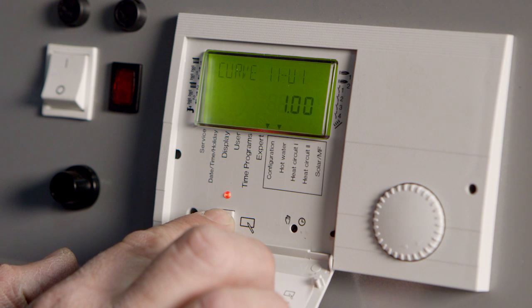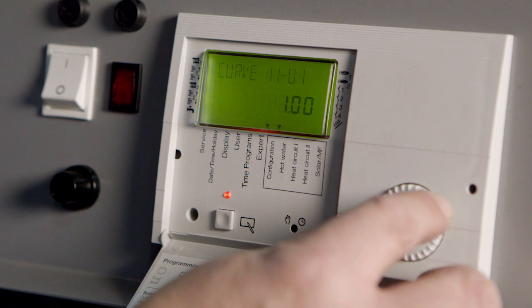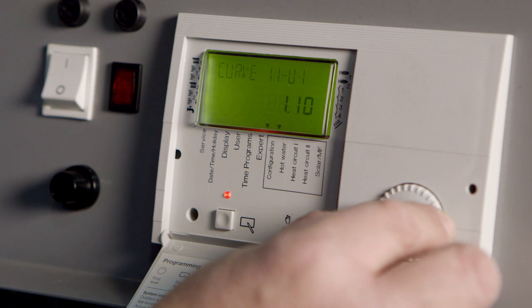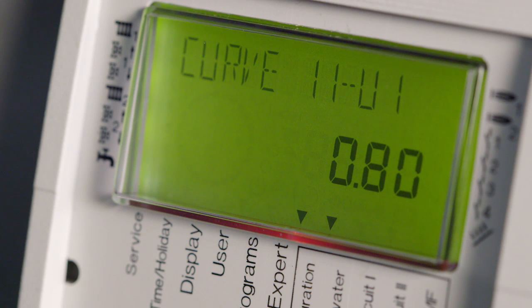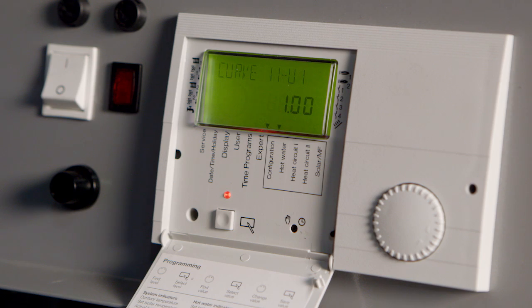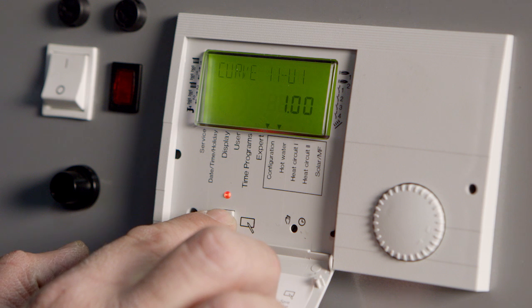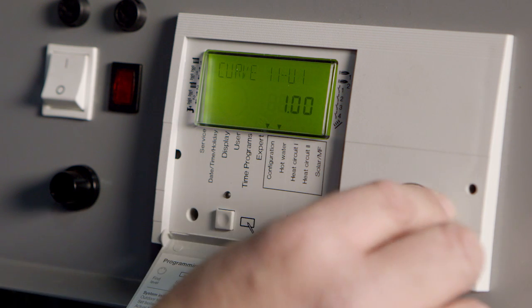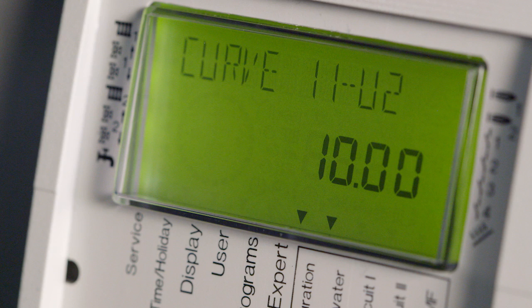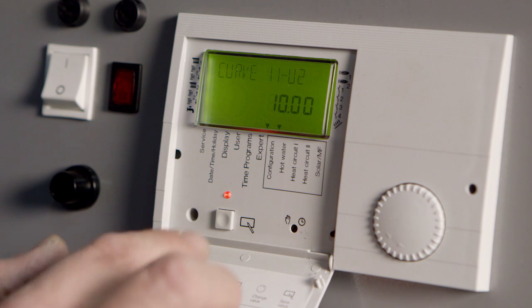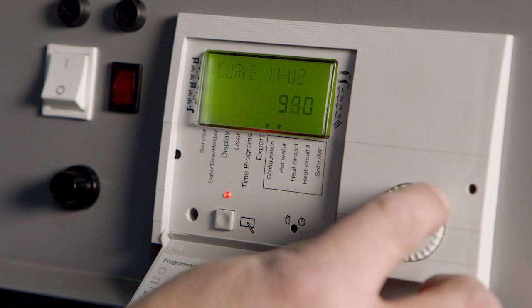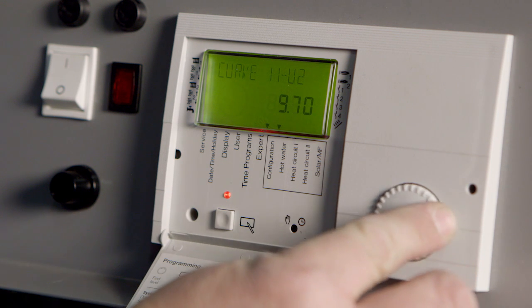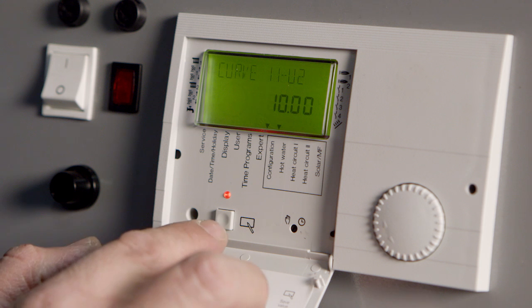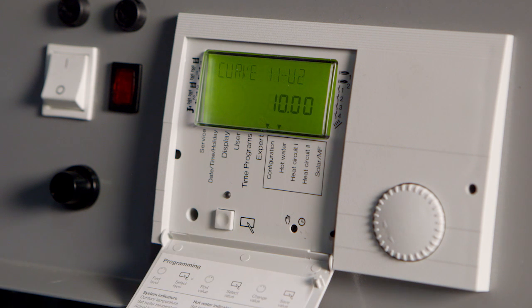Press the program key again. Enter the desired low voltage limit for U1 by turning the knob. The voltage will increase or decrease in 0.10 volt increments. When you get to the low voltage limit you want, press the program key to set the voltage. Turn the rotary knob again clockwise, scrolling until you find curve 11-U2. Press the program key and the red light will glow again. Enter the high voltage limit you want for U2 by turning the knob like this. Press the program key again to set the U2 voltage.